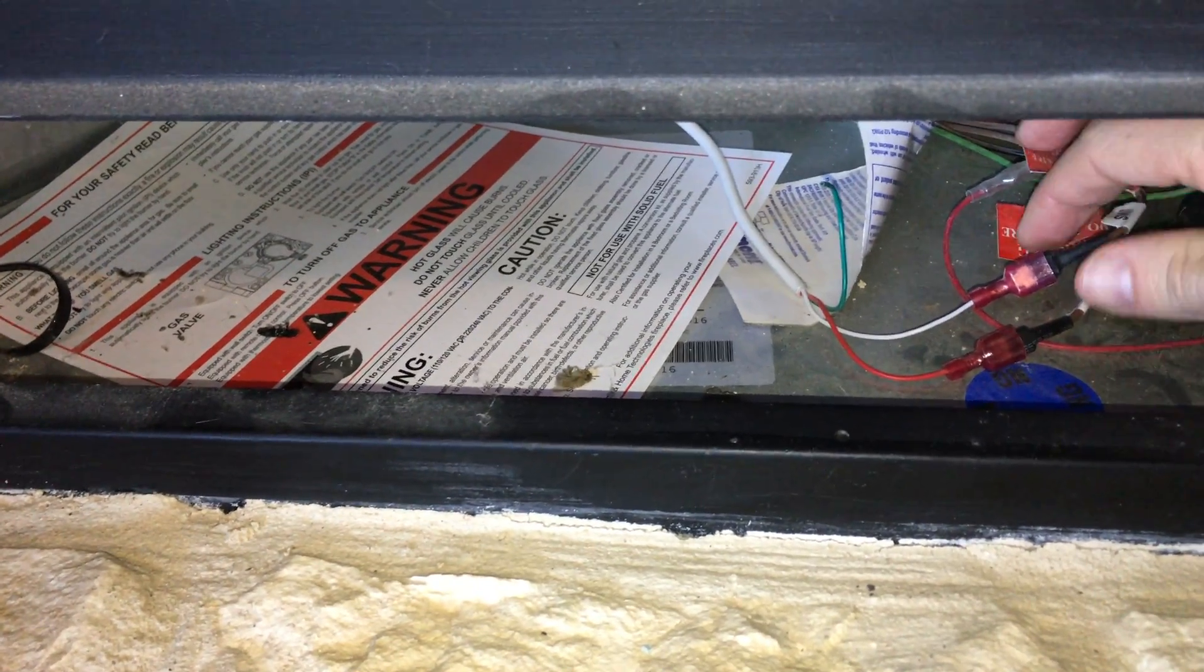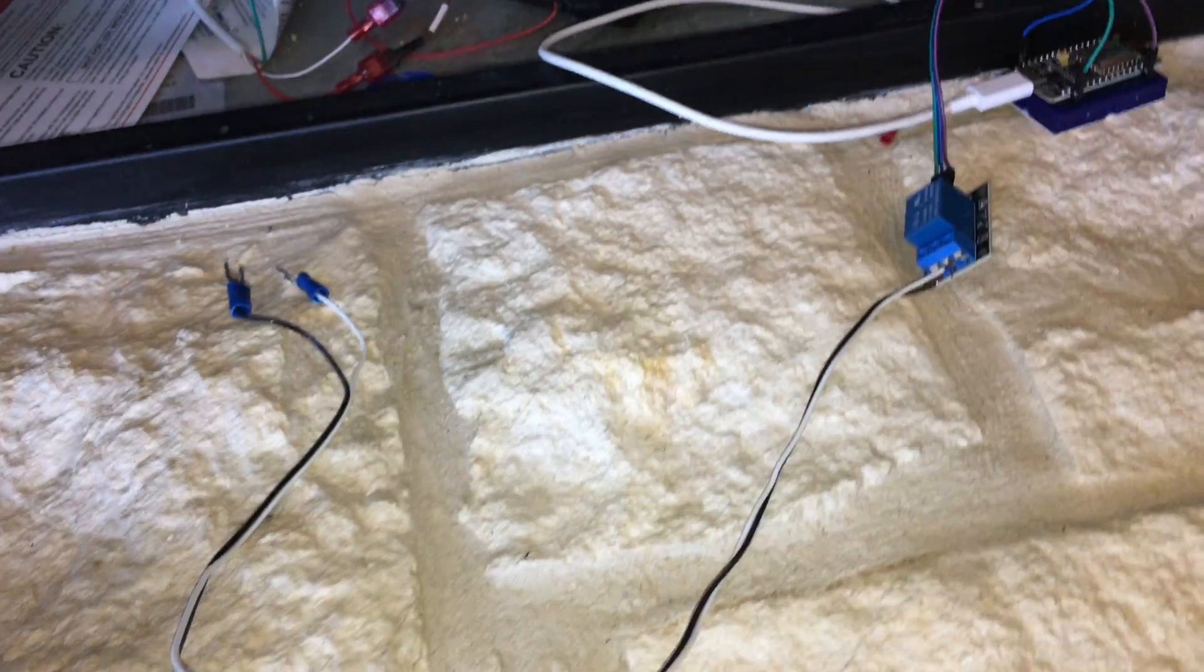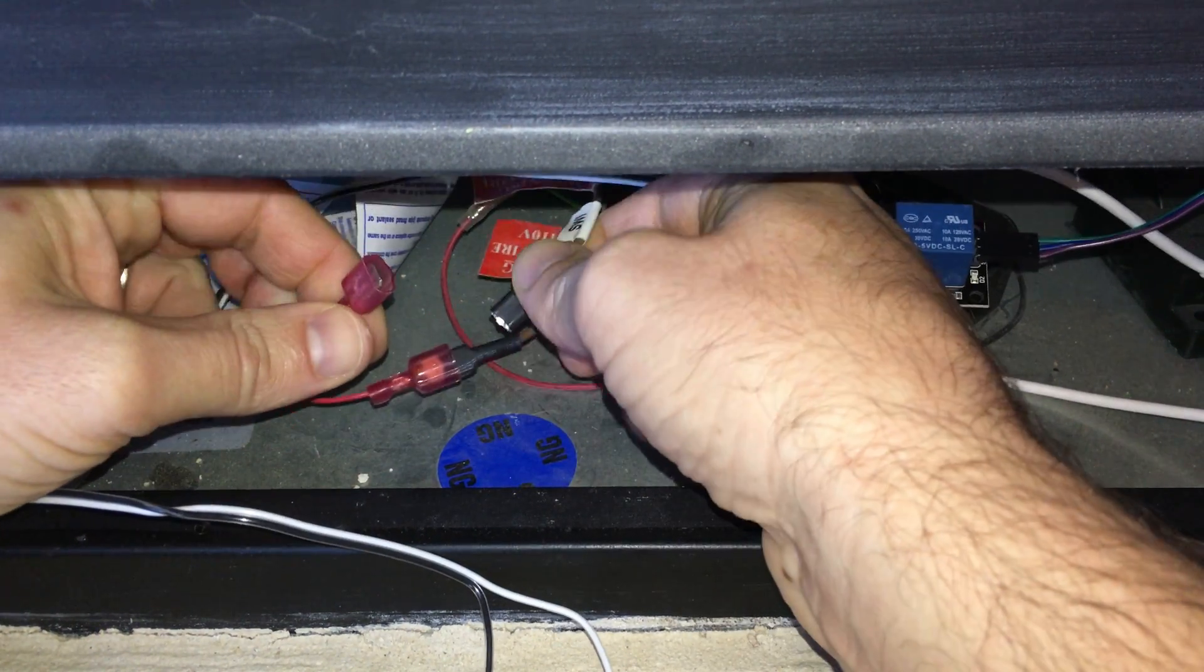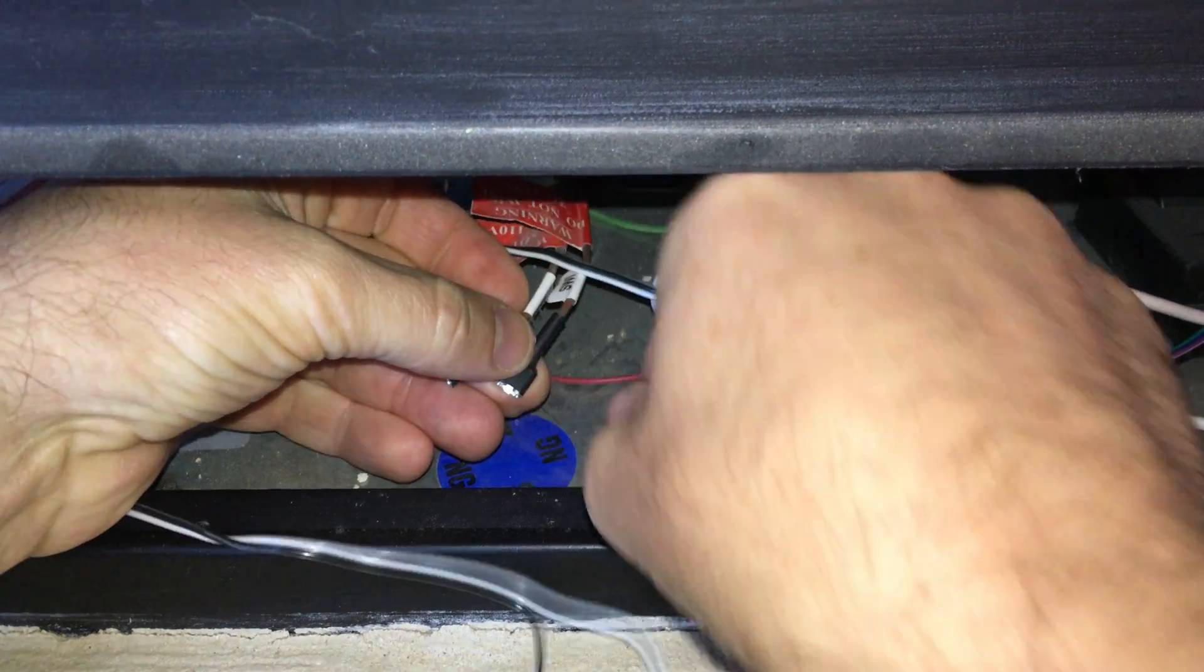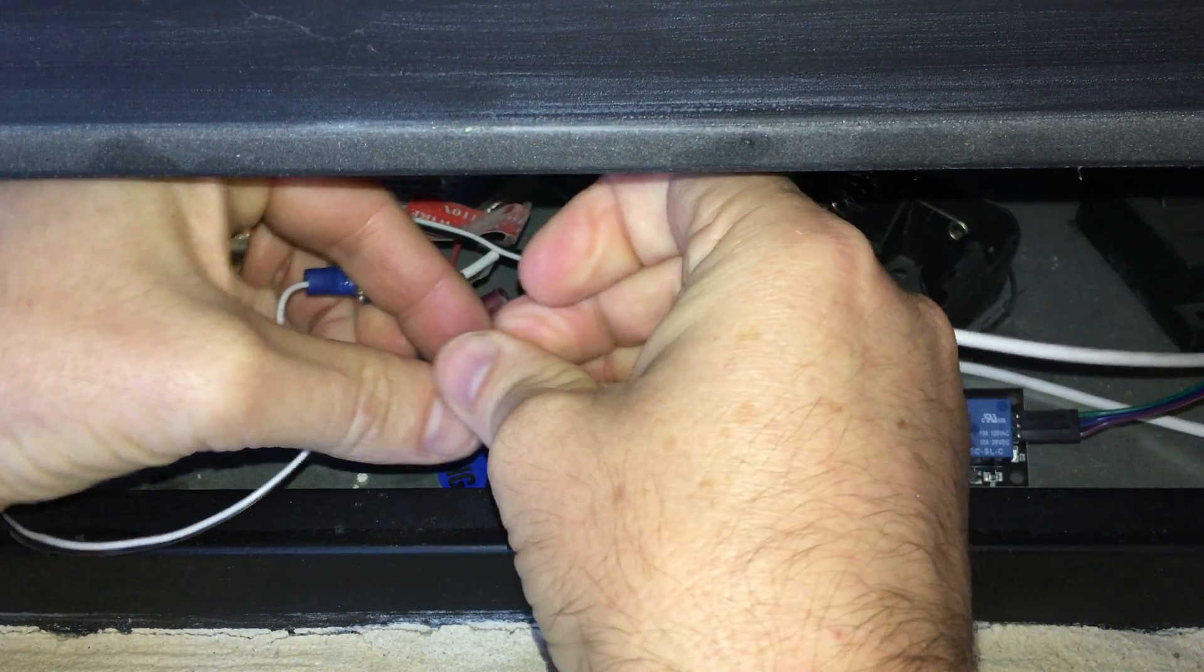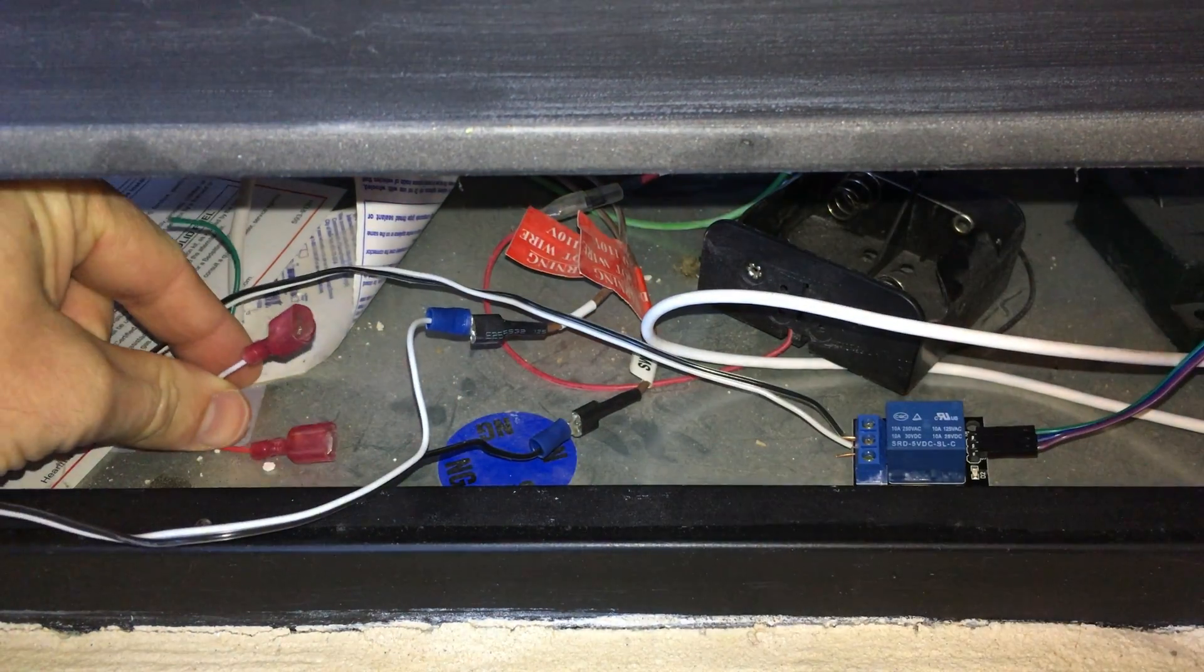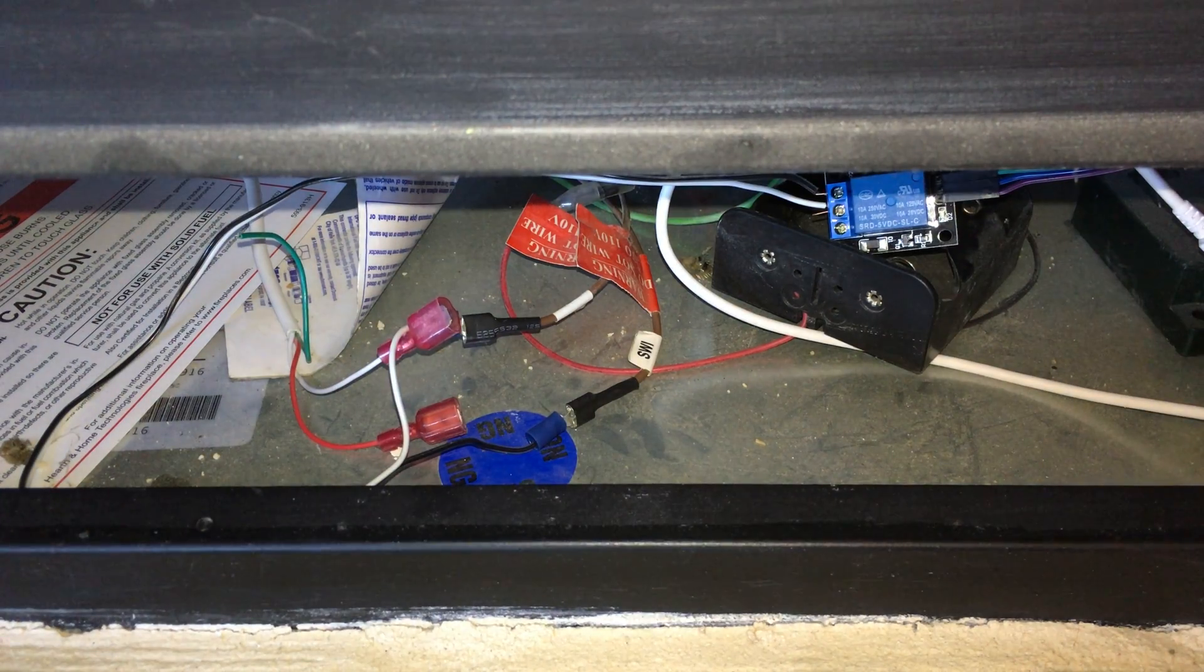Simply unplug these two wires from the switch and then plug these two into the two little spade connectors that go into your relay. So let's disconnect the wall switch from our control unit. And then we'll plug in the spade connectors going into our relay. It does not matter the order of these, which one plugs into which. We won't use those anymore. Make sure that your contacts are isolated and not getting shorted out on the fireplace.